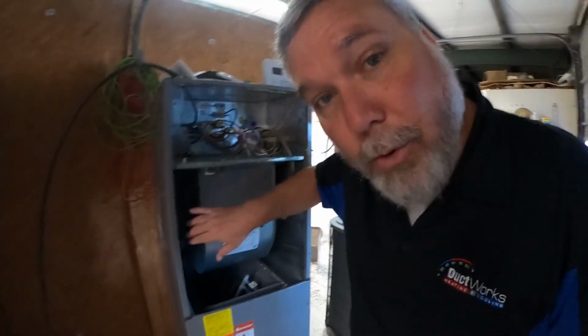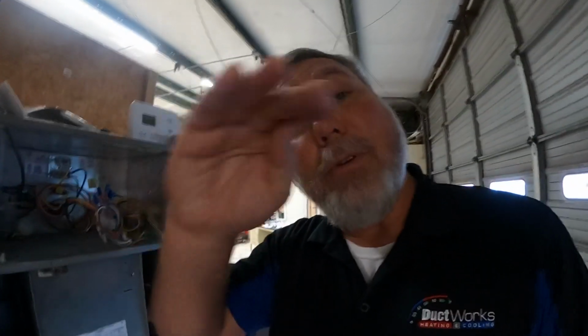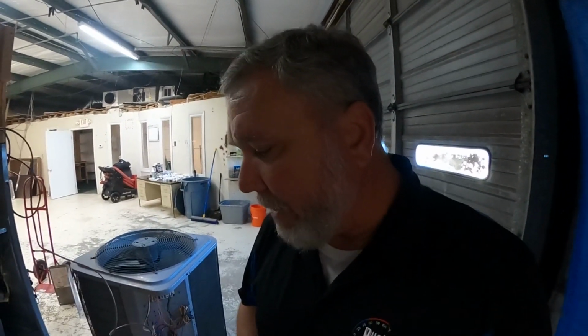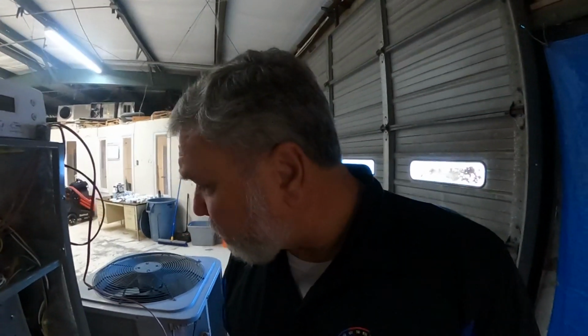We also check the indoor blower. We want to make sure that there's no debris in there, no dust. As time goes on, if it's not cleaned, dust builds up in the little fan, like little scoops. And once those fill up, you don't move airflow like you once did. We also check these coils. We make sure that they're good and cleaned out, with no dust or debris in that as well. So that's just some examples of things that we do on the maintenance side for heating. We also clean those drains out again. Even though the drains are mainly used in the summertime, we go ahead and flush them again in case there's any dust or anything. We don't want that to turn into mush or harden up in the wintertime when there's no water going through there. But yeah, that's pretty much maintenance in a nutshell when it comes to heat pump maintenance.